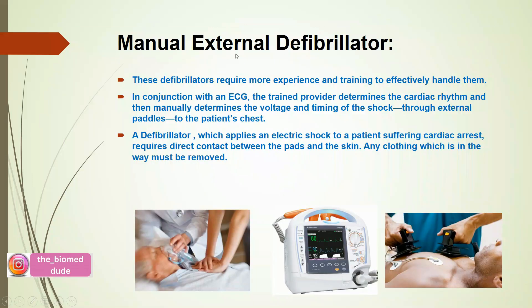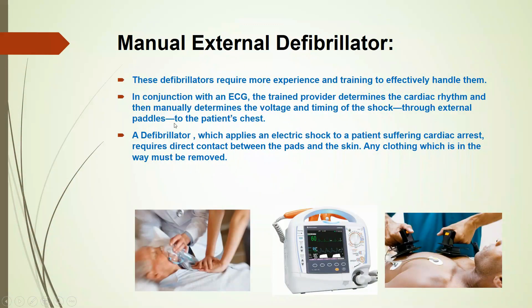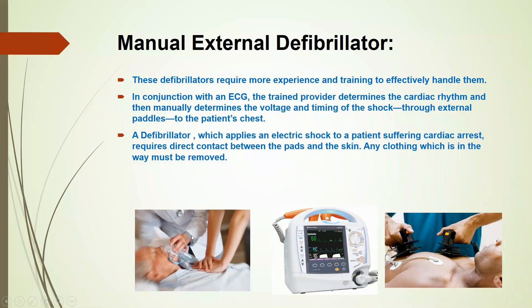The first type is the manual external defibrillator. These defibrillators require more experience and training to efficiently handle them. In conjunction with ECG, the trained provider determines the cardiac rhythm and then manually determines the voltage and time of the shock through external paddles to the patient's chest. Here are three different pictures showing CPR being performed on the patient, then adjusting the joules as per requirement and delivering shock to the patient.